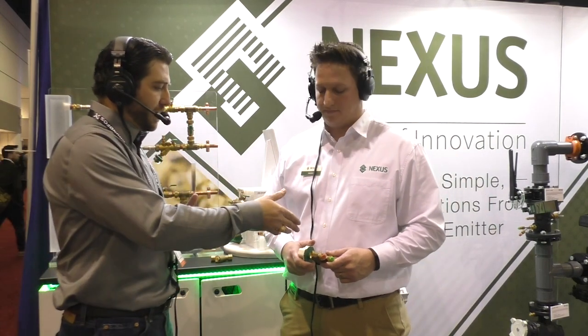Anytime you're joining back from the branch lines to the main return, you're going to want to have one of these balancing valves, and we're seeing pretty low flows on that, half to 2 GPM per branch line. So the manual works great. Same way there, you're going to tie in, read your differential pressure across the valve, and look at your chart to see what your flow rate is.